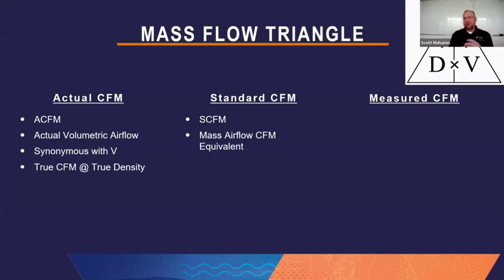By the way, 7.5 pounds is like 100 CFM at 70 degrees, and barometric pressure of 29.92. So there's a way to get to the CFM value by referring to the mass. And so simply what we do with the mass number is we divide it by standard density and we convert it into a CFM equivalent number. So the mass flow or SCFM value is simply the airflow you're going to have in volume if you were at that standard density condition at 0.075 pounds per cubic foot. And really this value is synonymous with the M on this triangle.